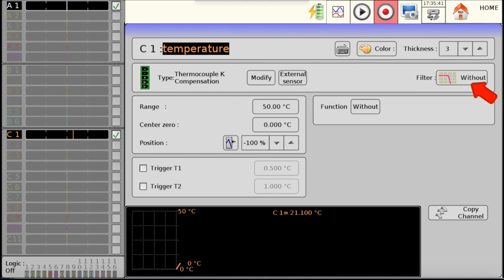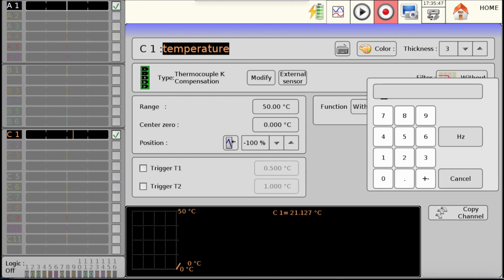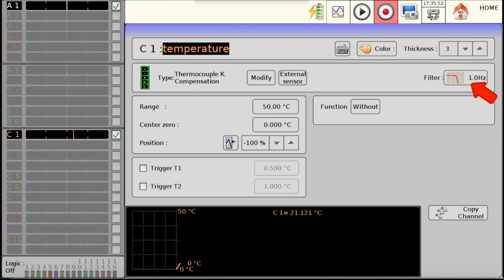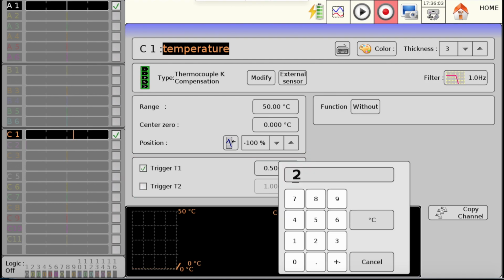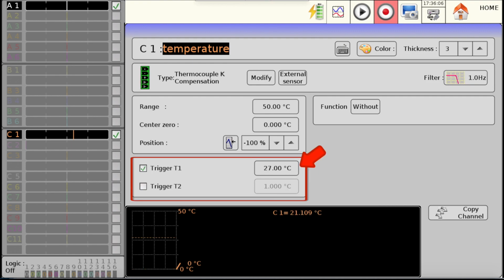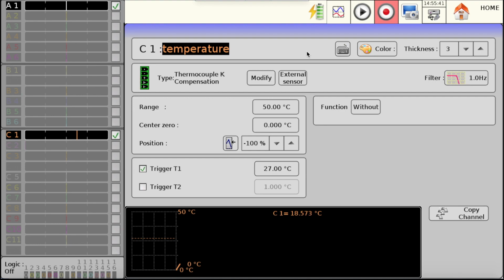You can set a filter on the channel to cut all frequencies that would be higher than the recorded signal. In our case, we apply a 1 Hz filter in order to cut all frequency higher than 1 Hz. Let's define a threshold at 27 degrees. Above this temperature, the recording will start. Finally, you can copy this configuration of this channel to any other channel that would be identical. Our thermocouple channel is now configured.